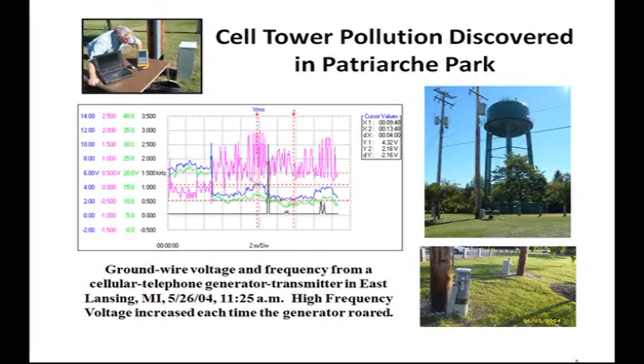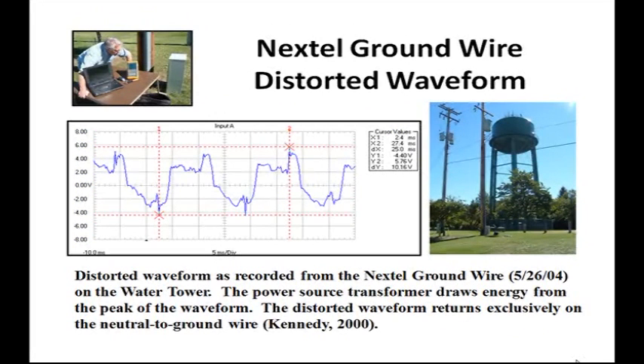So we measured the voltage, current, and frequency from the neutral to ground wire and found that AC, DC, and peak-to-peak current increased each time the generator was heard roaring from our recording site in the park. The neutral wire was bonded to the city water system, so the same voltage and current were measured on the water systems of homes in the neighborhood.